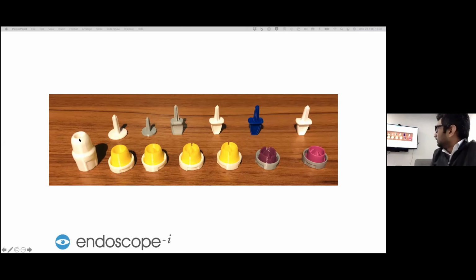But the other thing was that you can see here, this thing in total is probably about 2 centimeters long. And what that does is it basically fixates 2 centimeters of your flexible scope, and it reduces the flexibility of your endoscope. So it was actually quite difficult to navigate the scope once it was in the nose, around, it fixed it too much. And so that's why we immediately changed those two elements into a two-part mechanism. So just an outer and an inner.